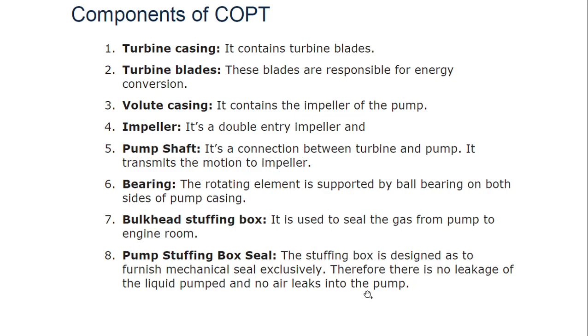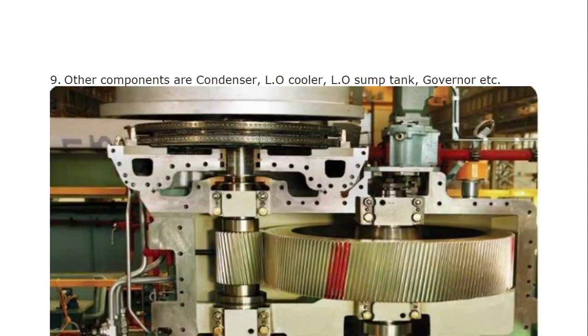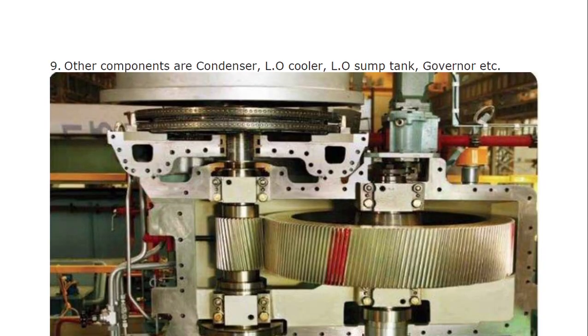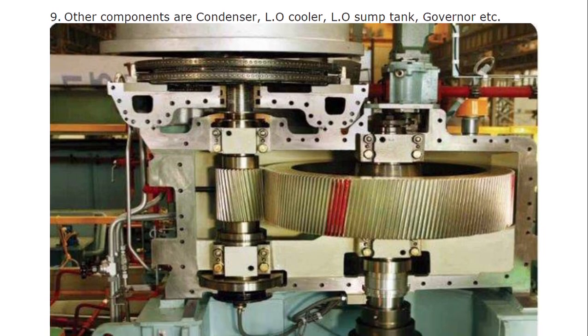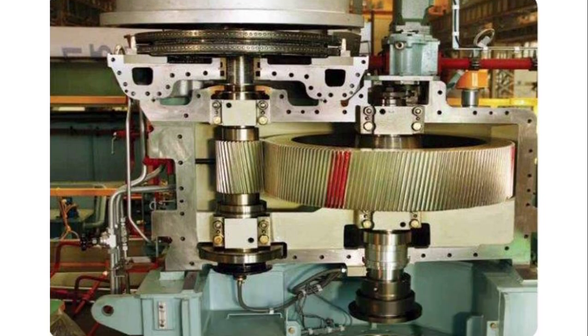The bulkhead stuffing box is used to seal gas from the pump to the engine room. The pump stuffing box is designed to furnish a mechanical seal exclusively, so there is no leakage of liquid from the pump and no air leaks into the pump. Other components include the condenser, lube oil cooler, lube oil sump tank, and governor.